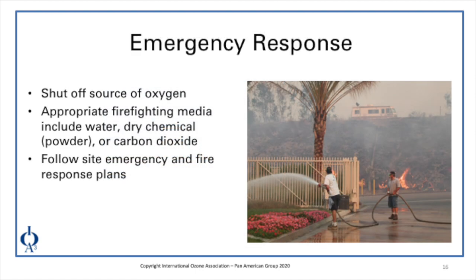In the event of a leak, the emergency response would first shut off the source of oxygen, notify the appropriate emergency response facilities, and follow your emergency response and fire response plans. Ideally the fire department will respond and it's not necessary for your staff to respond. But in the event that there is a small fire that needs to be addressed, some appropriate firefighting media include water, dry chemical powder, or carbon dioxide.